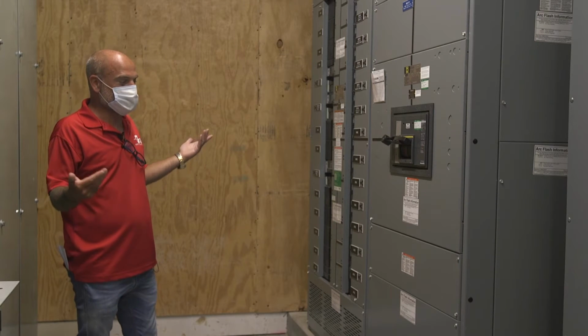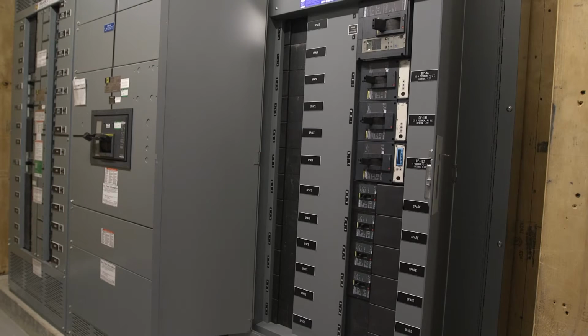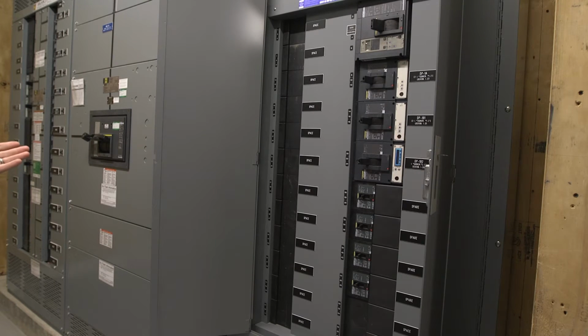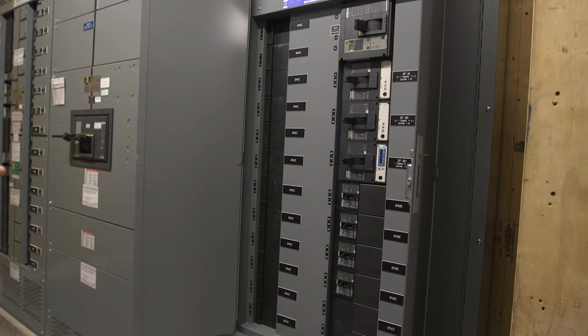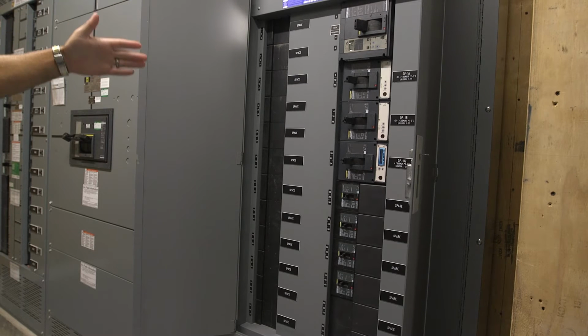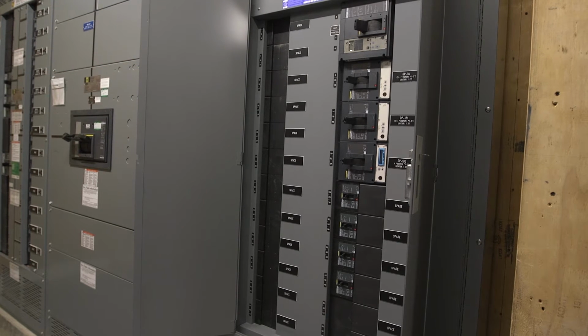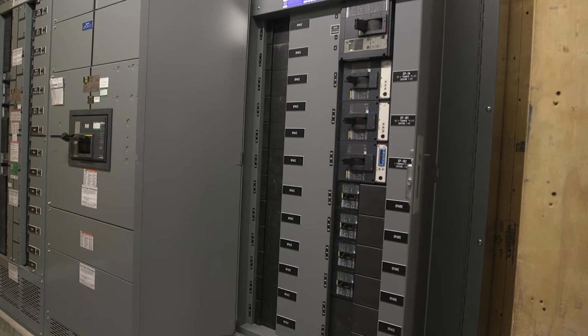So that's basically it. This is a Square D I-Line panelboard. Pretty much the same basic idea of load distribution, with a little different construction. You have your main coming in, and you have your distribution breakers that are feeding out to your downstream sources. This has front to back busing, and the breakers actually plug into the side of this panel. So it's just a little different when you open it up. There's one screw that holds the breakers in place.